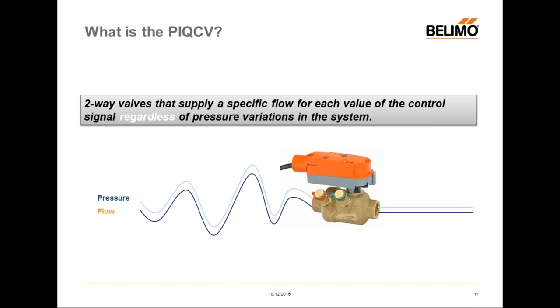For PI-QCV, it's a two-way valve that supplies a specific flow for each value of control signal, regardless of pressure variation in the system. When zones close, additional operating zones get more water than needed with a pressure-dependent valve. With pressure-independent valves, when zones close, operating zones maintain their design flow.